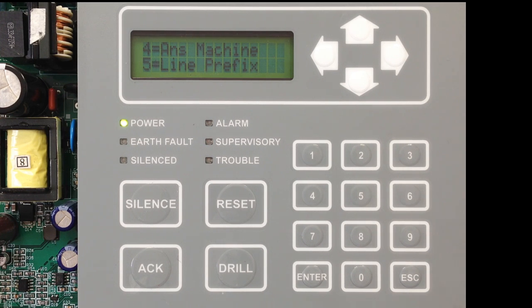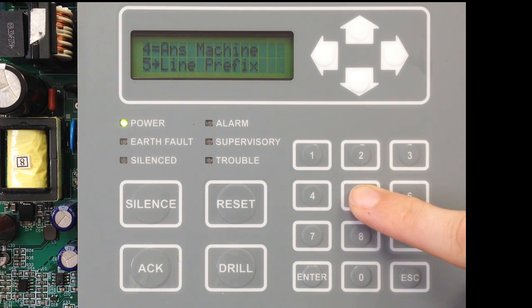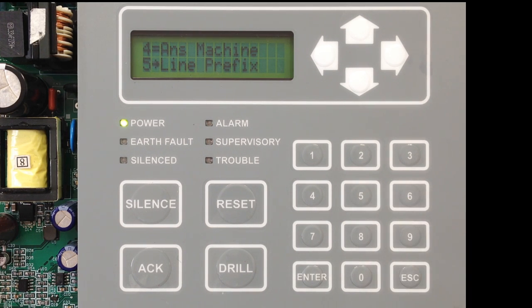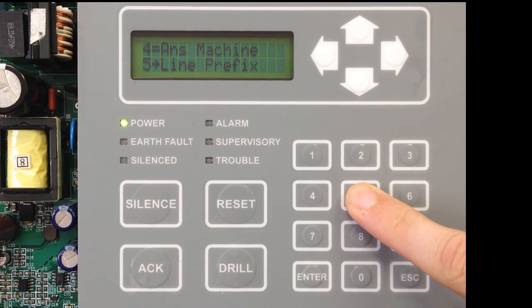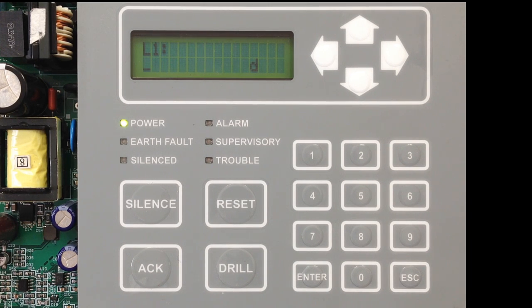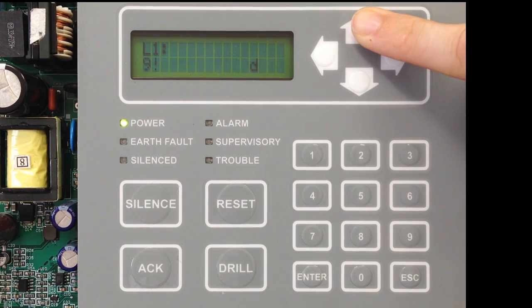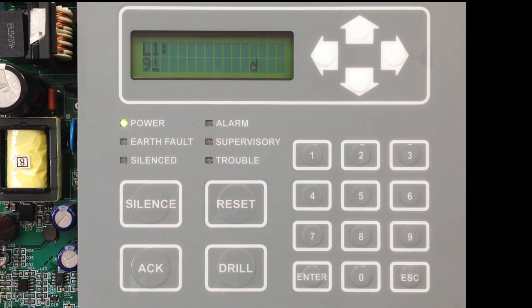The next option is for entering a Line Prefix. This has to do with using a phone system where you would need to dial 9 or something else to get out of that system. So select option 5, and here you can enter 9. You can use the up and down arrows to move through characters you may need to get through that phone system.